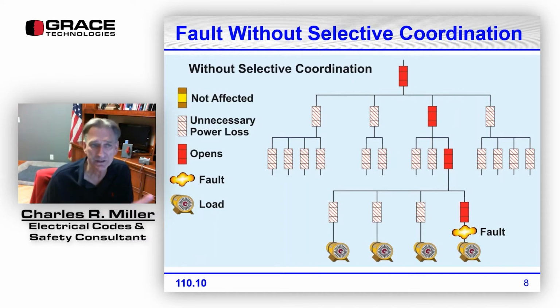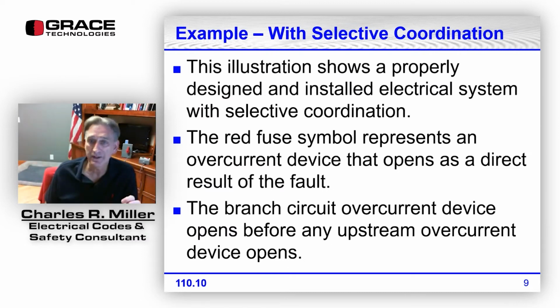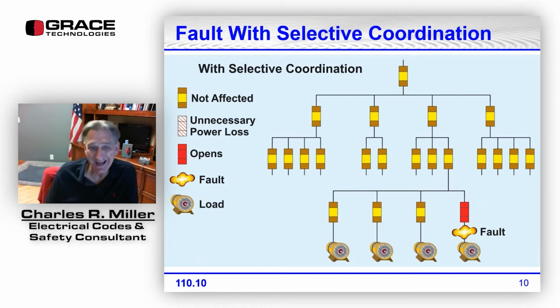In the next example, it's going to show a fault that has selective coordination. The next illustration shows a properly designed and installed electrical system with selective coordination. The red fuse represents an overcurrent device that opens as a direct result of the fault. The branch circuit overcurrent device opens before any upstream overcurrent device opens. All right, so this one is designed and installed with selective coordination. Now we have a fault in a motor, and it is limited to that branch circuit for that motor only. Nothing else upstream is affected.